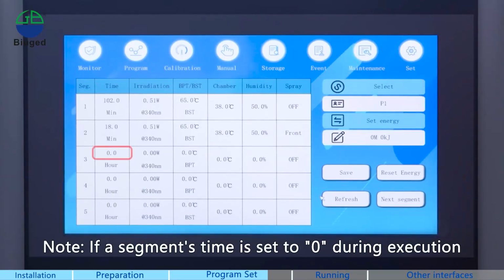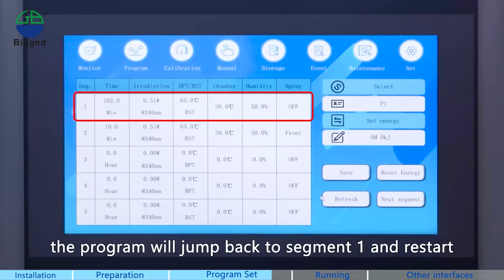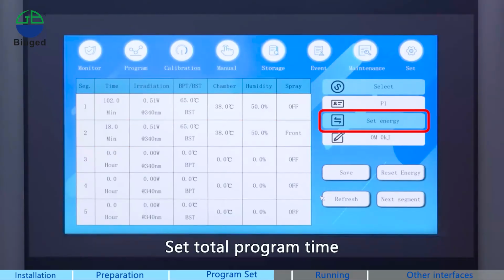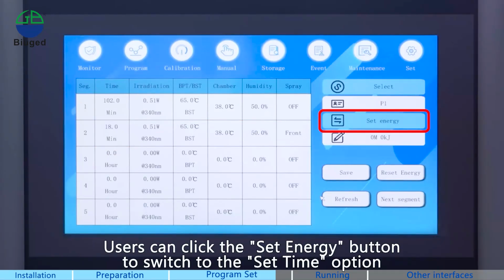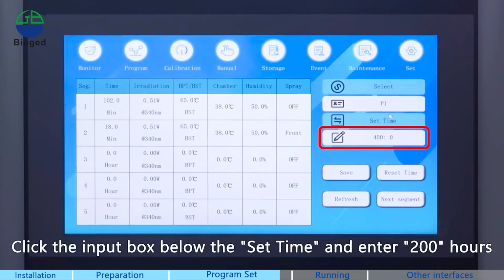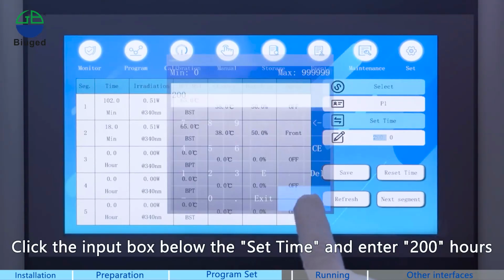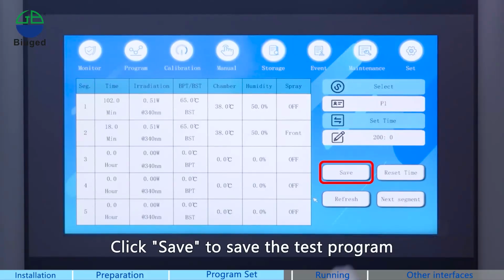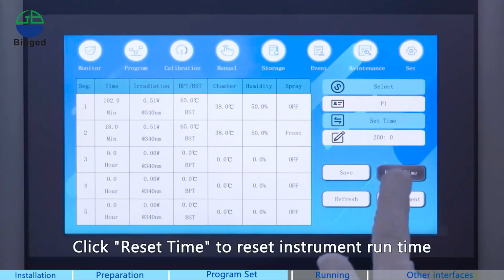Note, if a segment's time is set to 0 during execution, the program will jump back to segment 1 and restart. Set total program time. Users can click the Set Energy button to switch to the Set Time option. Click the input box below the set time and enter 200 hours. Click Save to save the test program. Click Reset Time to reset instrument run time.